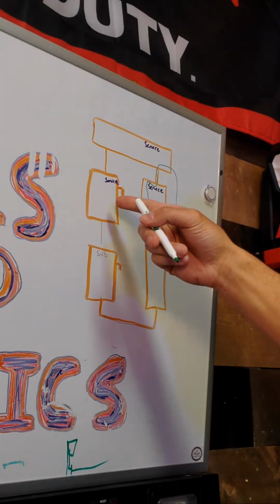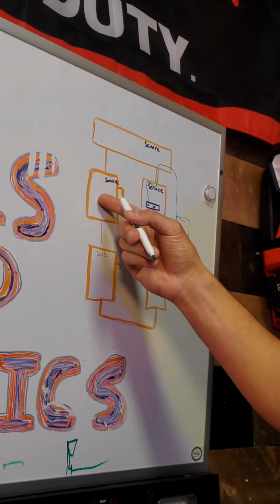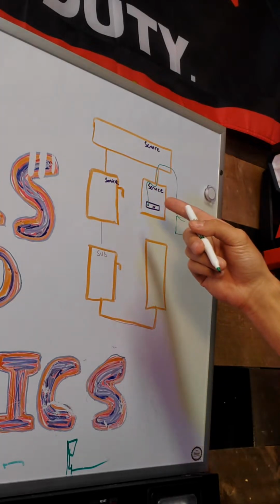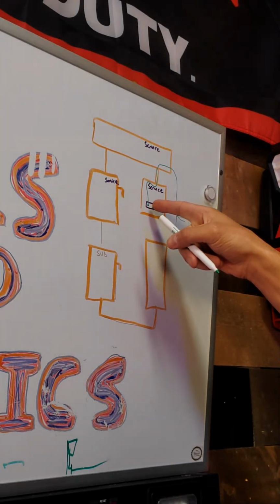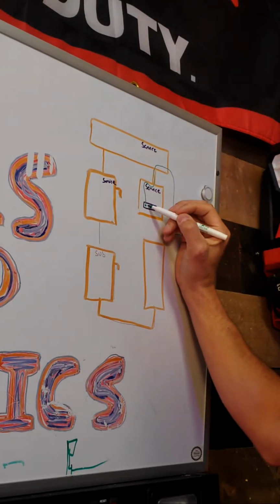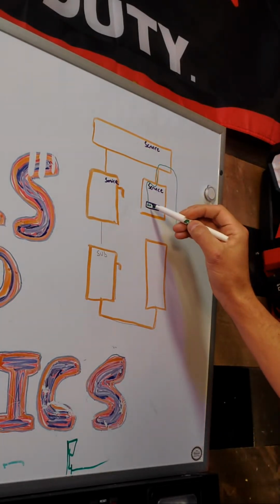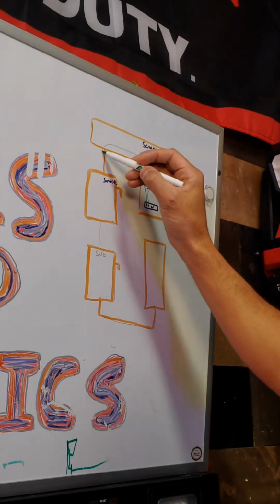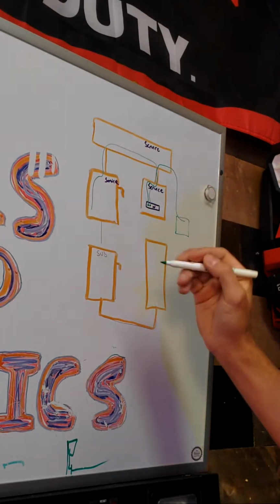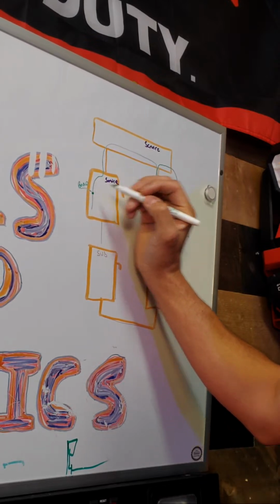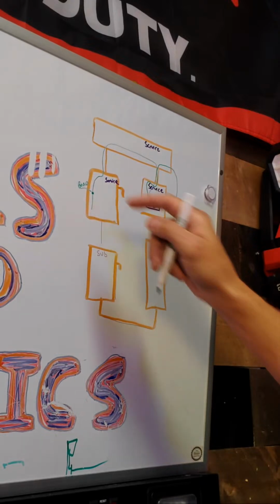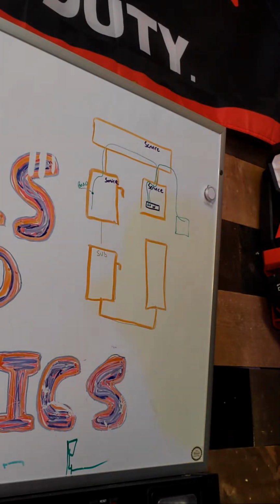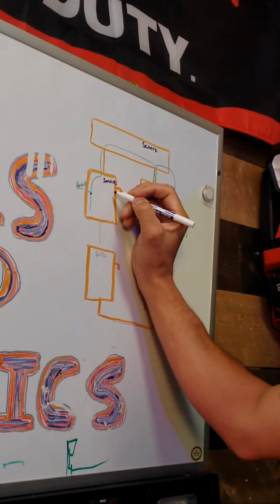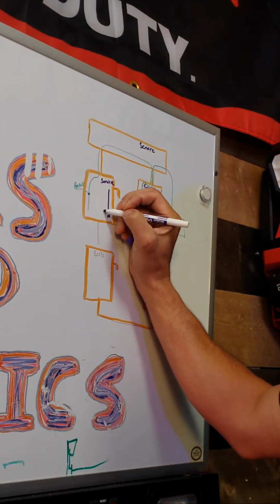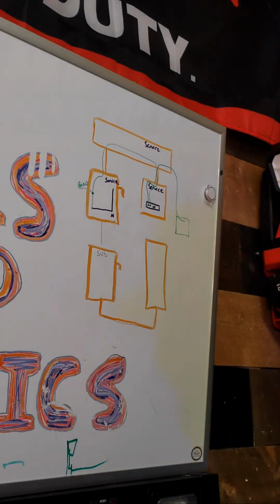And they went down into the service equipment, into the tap can, and they bonded the neutral here, which is something you would do—I mean, you could if you wanted to. I like to see my service grounds inside my first means of disconnect, but they bonded it here, so they did that. And then they came back off of this and ran it to the service, and they also bonded there, and also tied it to the neutral. So if we draw a neutral bar here, they bonded it all together inside there.